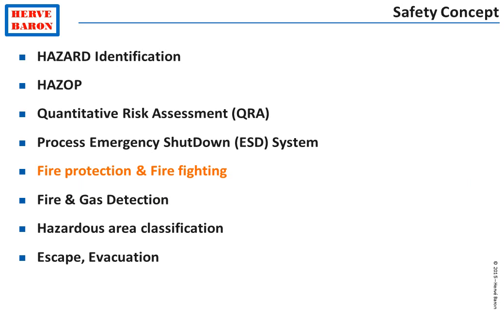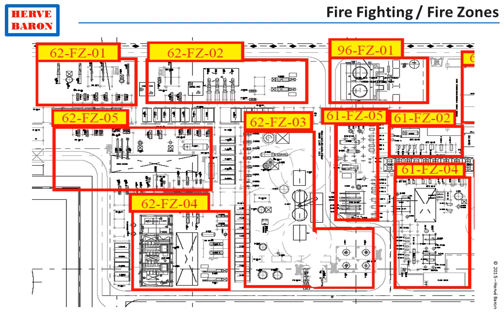Safety designs the plant fire protection and firefighting system. As we have seen in the plant layout, separation distances are kept between units. This segregation limits the extent of a fire within one unit, which is then called a fire zone. This helps to limit the capacity of the firefighting system to the needs of one fire zone instead of the complete plant.